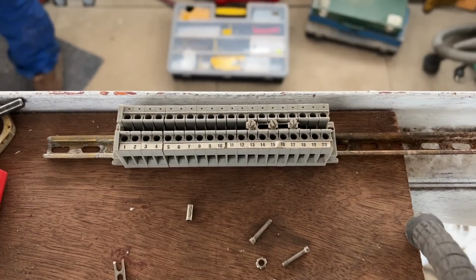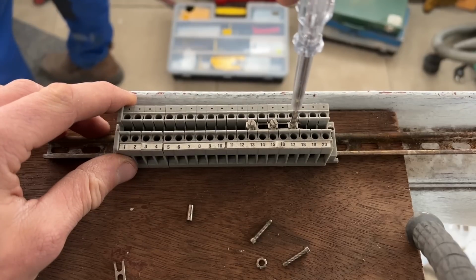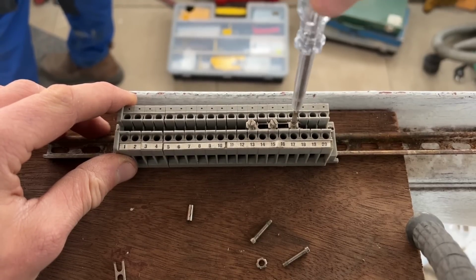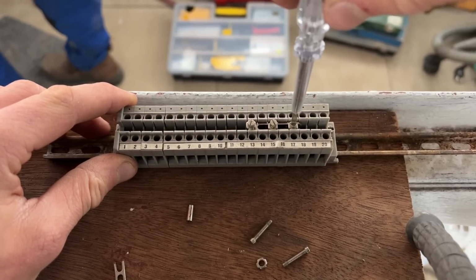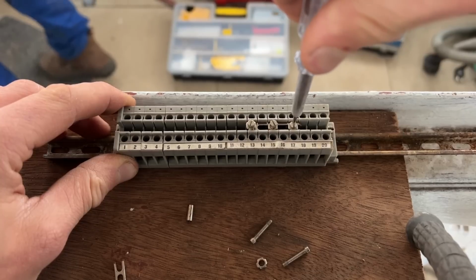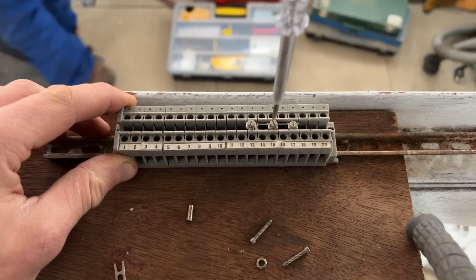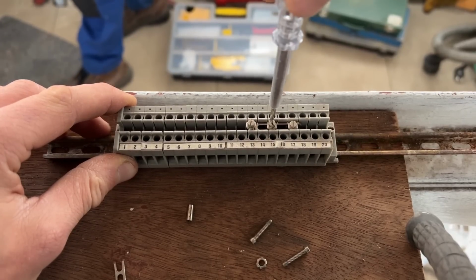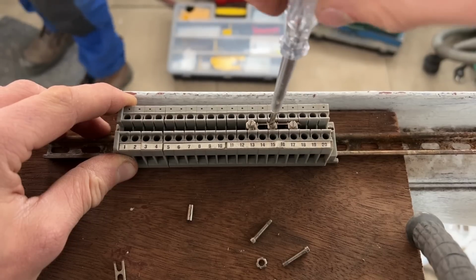These days it's very common to use terminal blocks in electric cabinets and switchboards. Every terminal would have a number that corresponds to a number on the electric drawing, making it easy to find which wire does what, because it is impossible to follow the individual cables in these cabinets. I personally prefer to use a 2-core cable, running straight from the breaker to the consumer, with no terminal blocks in between. Because it makes the system simpler and less connections make for less possible errors.